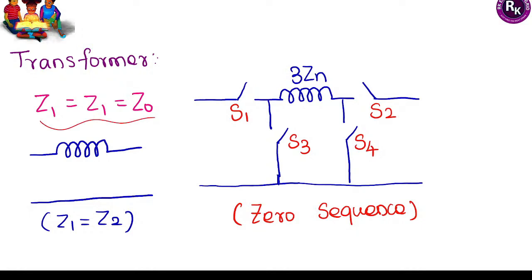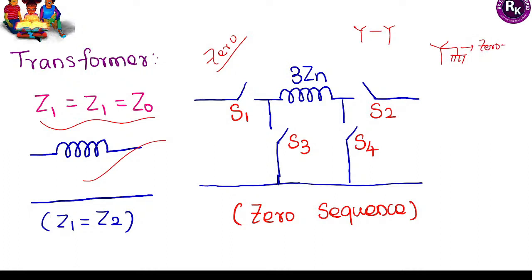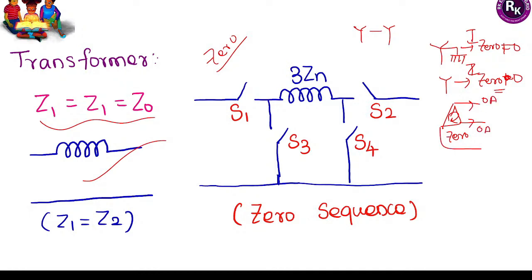For transformers: positive, negative, and zero sequence impedances are all equal. However, zero sequence network behavior depends on transformer connection type. For star connection with neutral grounded, zero sequence component exists; without neutral (isolated), zero sequence becomes zero. For delta connection, zero sequence circulates internally but does not appear in the line. Common transformer connections (star-star, star-delta, delta-delta, delta-star) each have different zero sequence network configurations.